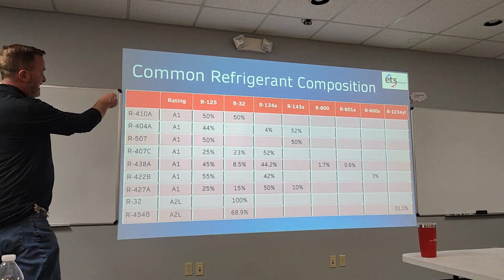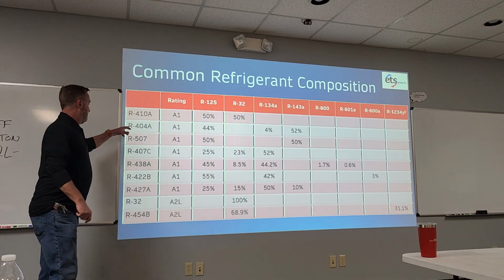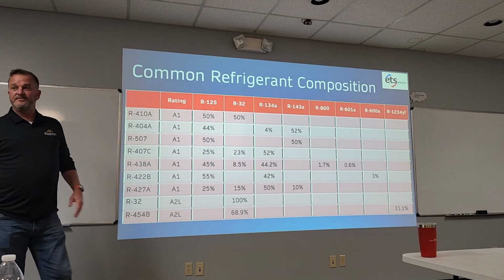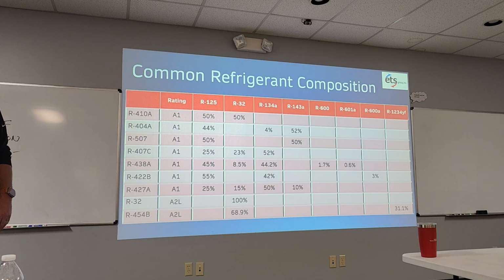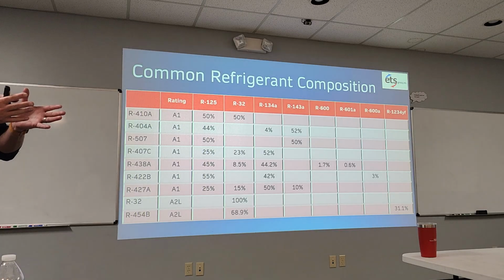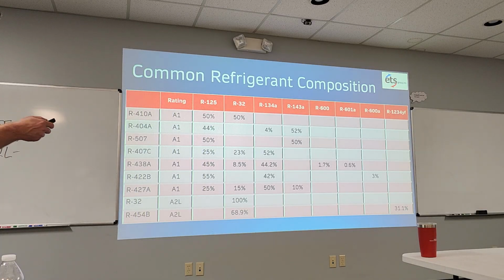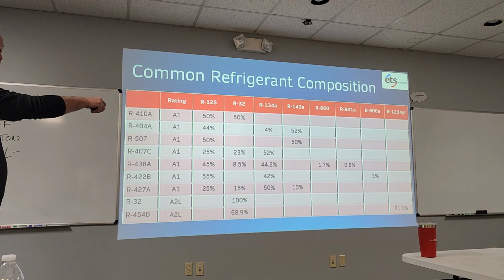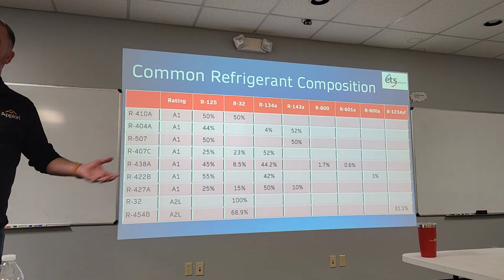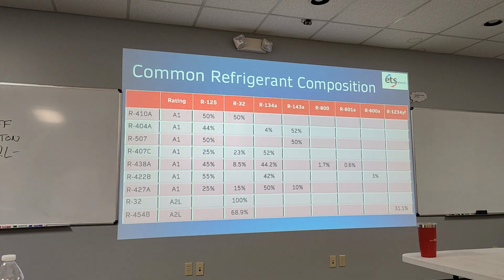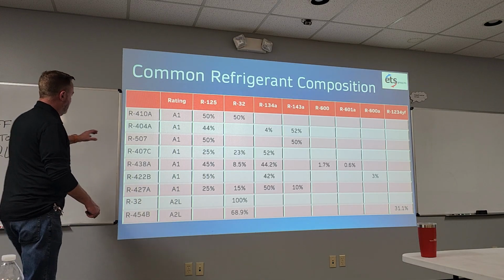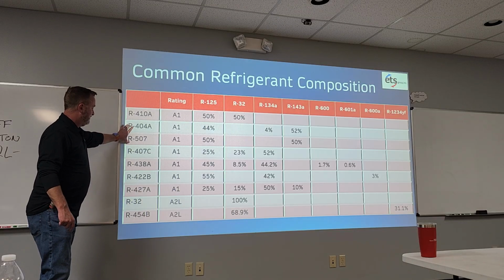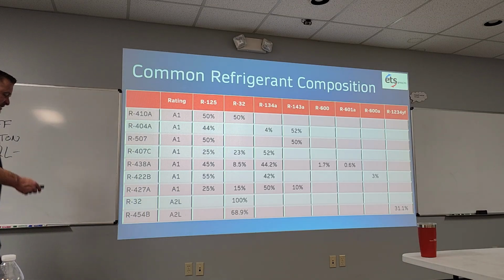So they have allocations of each of these refrigerants. So, okay, they're banning 404 in 24 states. What can I do? I can take my 125 from my 404 production, and what can I do? I can push it into my 410A production and make more 410A before the time runs out, right? So that's where the allocations come in, and that's why you're gonna see these two going away a lot quicker than most. They're gonna be very coveted and pricey when it comes down to it.